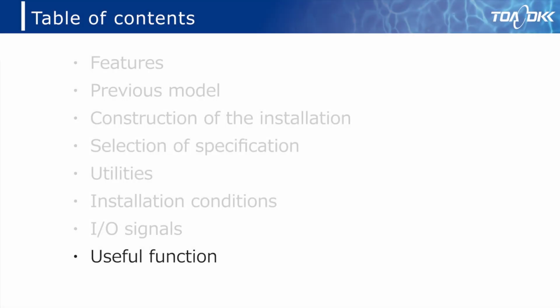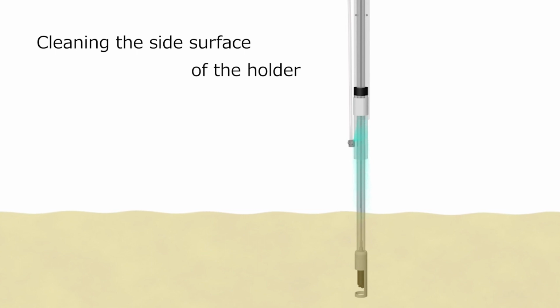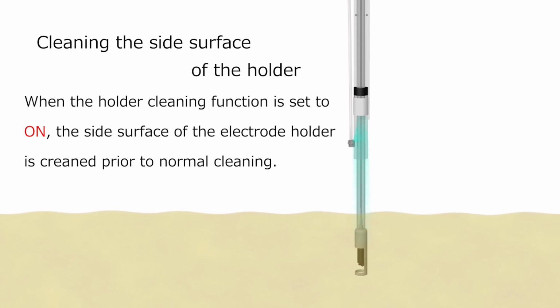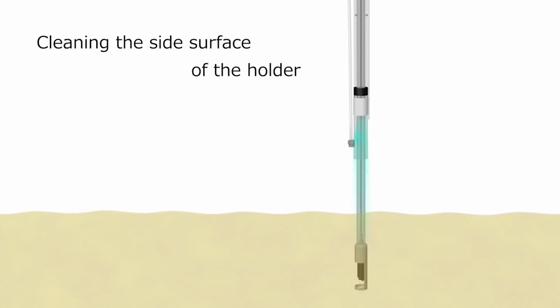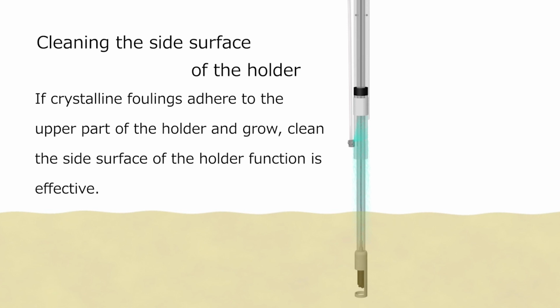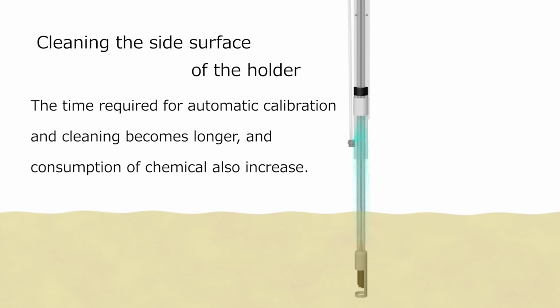Here are some useful features of MAC-1600 that will help users and maintenance companies. Holder side cleaning is also possible at the setting. When the holder cleaning function is set to on, the side surface of the electrode holder is cleaned before cleaning the electrodes. Water washing and chemical cleaning are performed with the electrode holder repeatedly rising and lowering. If crystalline foulings adhere to and grow on the upper part of the holder water surface, this side cleaning is effective. In this case, the time required for automatic calibration and automatic cleaning becomes longer, and the consumption of washing water and chemicals will also increase.